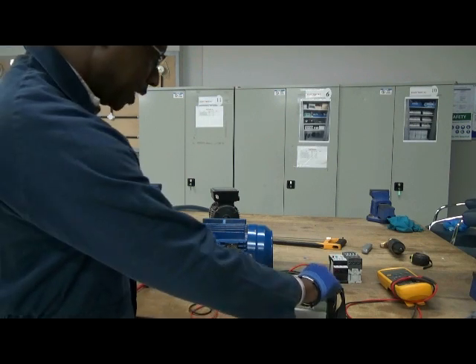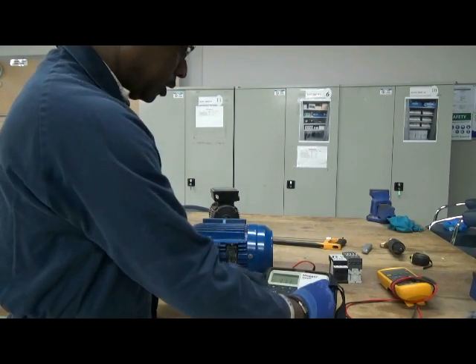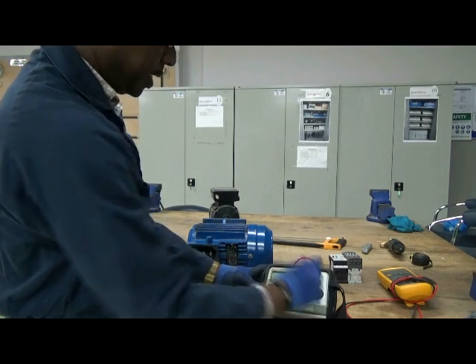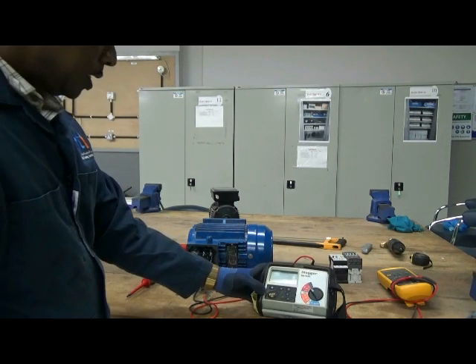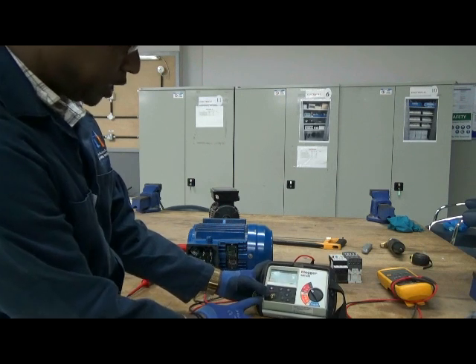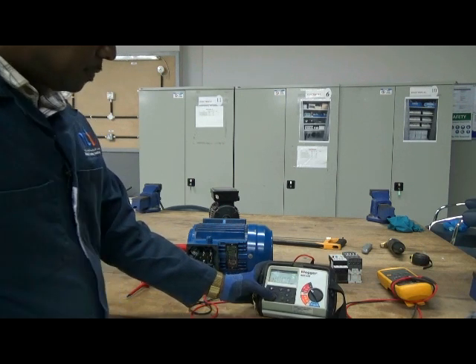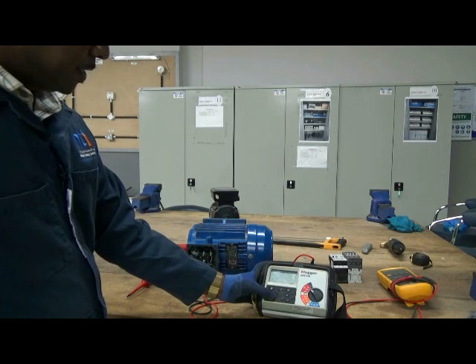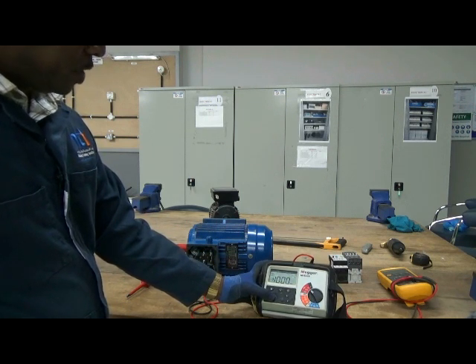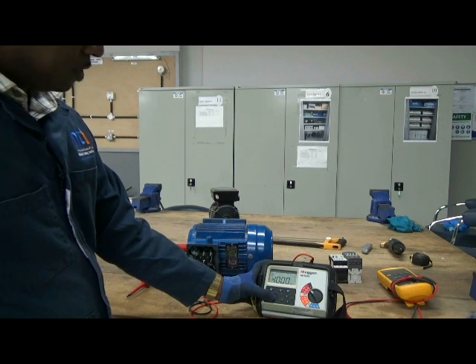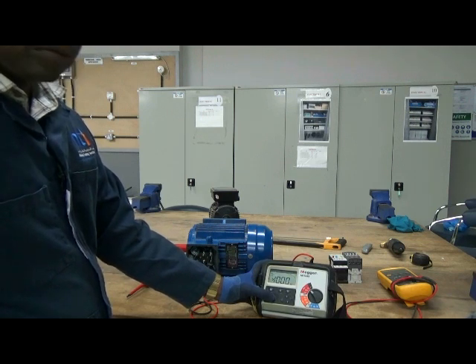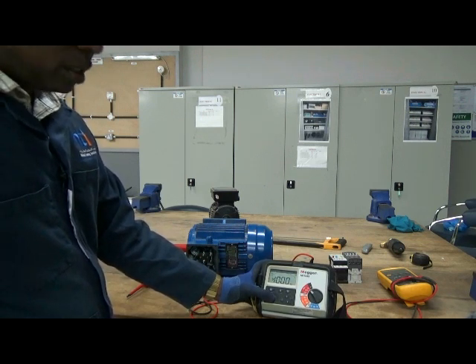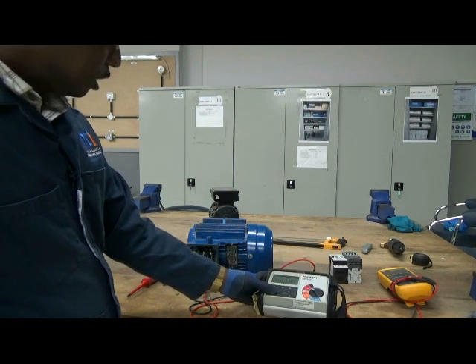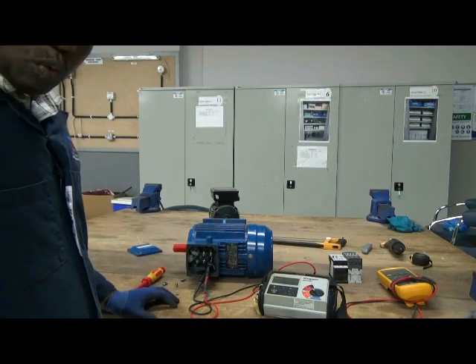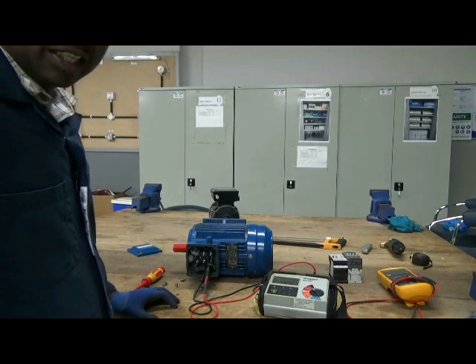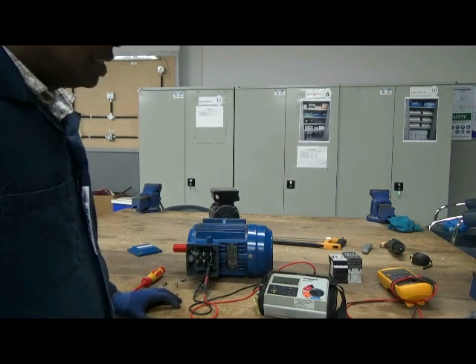Okay, so now I'm going to select a voltage. That's about 1,000 volts. And for me to test, I must press this test button. You can see it's testing, and it is showing me bigger than 1,000 mega ohms, 1,000 million ohms. That is the resistance between those two windings. If you have got such a resistance, then you have got good insulation.